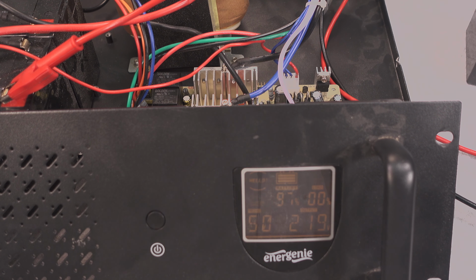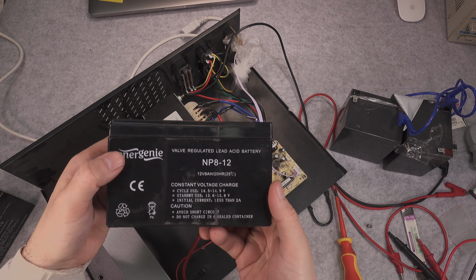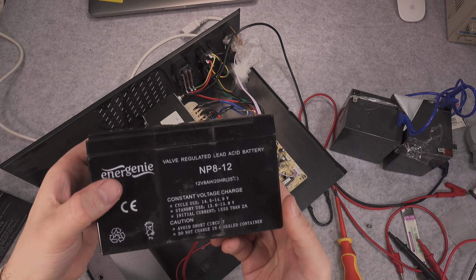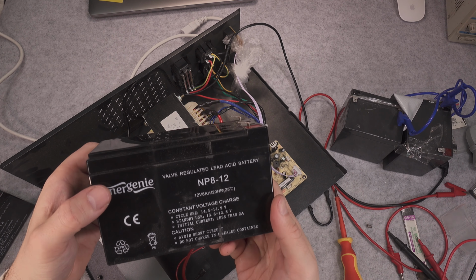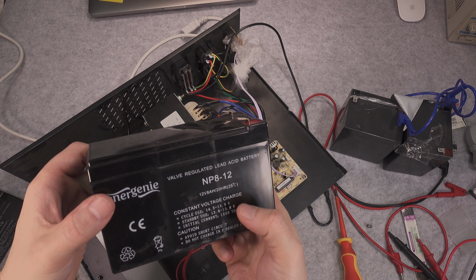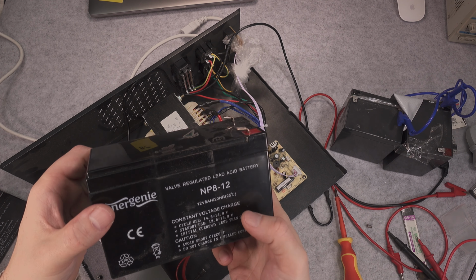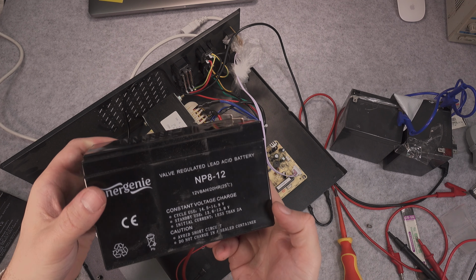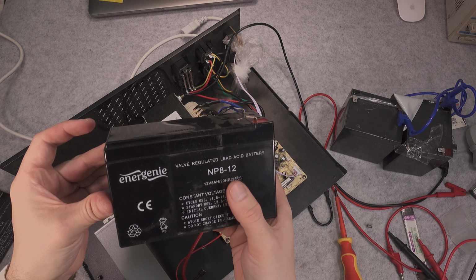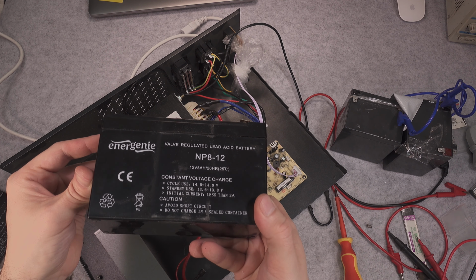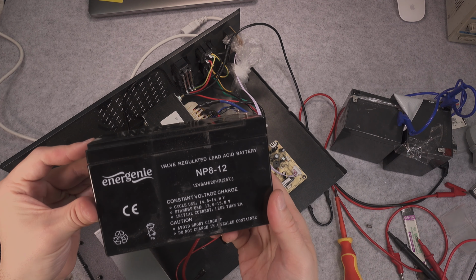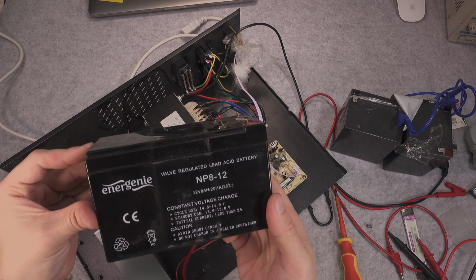This is the battery that was mounted inside. As you can see, it's branded with the same company that manufactured that UPS, so it's a quite interesting touch. It was OEM, 8 amp hour at 20 hour rate, so it's not a very good battery, because we should grab one rated for 15-minute discharge for UPS use.